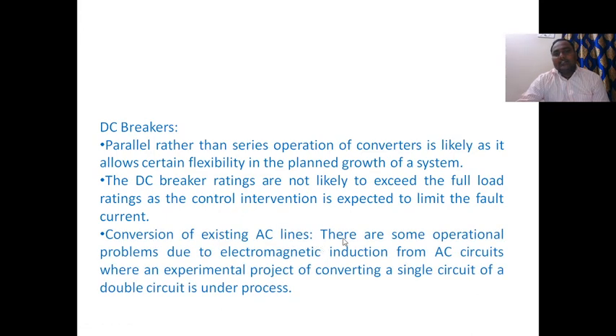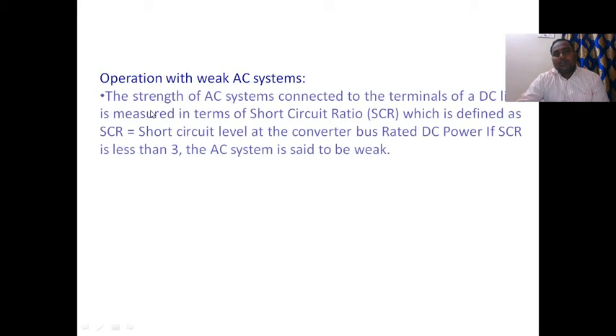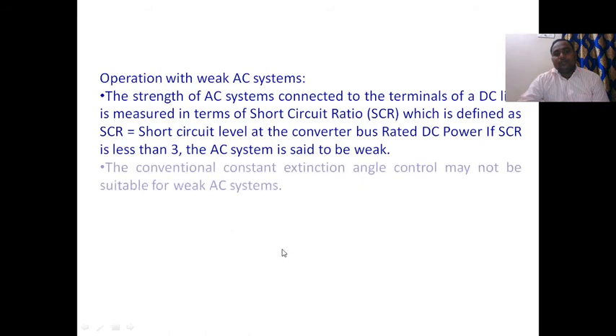Conversion of existing AC lines. There are some operational problems due to electromagnetic induction from AC circuits, where an experimental project of converting a single circuit of a double circuit is under process. Operation with weak AC systems. The strength of the AC system connected to the terminals of a DC link is measured in terms of short circuit ratio, defined as SCR equals the short circuit level at the converter bus divided by the rated DC power. If SCR is less than 3, the AC system is said to be weak. The conventional constant extinction angle control may not be suitable for weak AC systems.